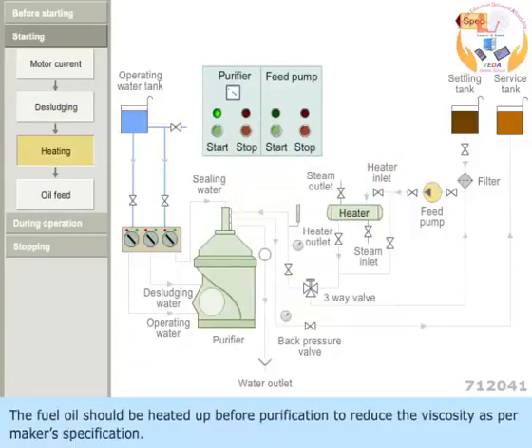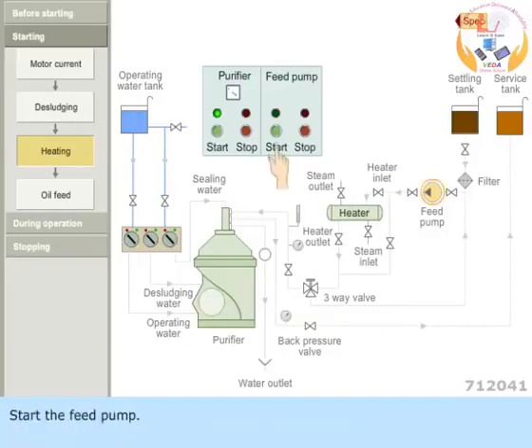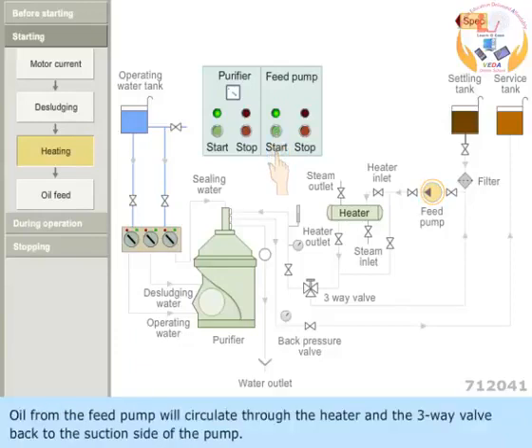The fuel oil should be heated up before purification to reduce the viscosity as per maker's specification. Start the feed pump. Oil from the feed pump will circulate through the heater and the 3-way valve back to the suction side of the pump.